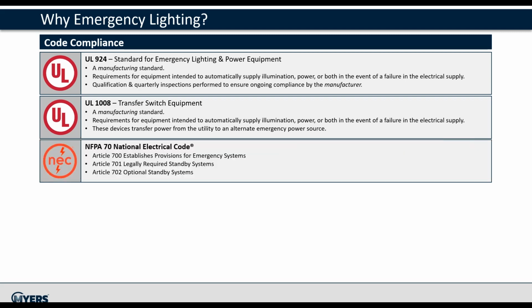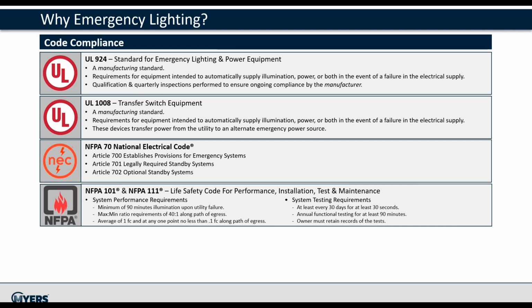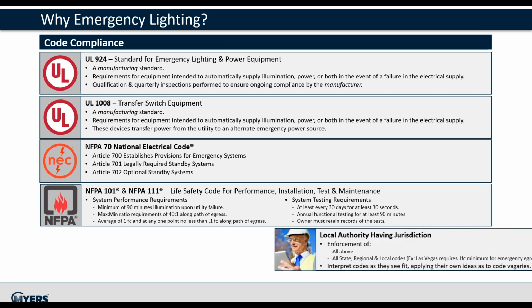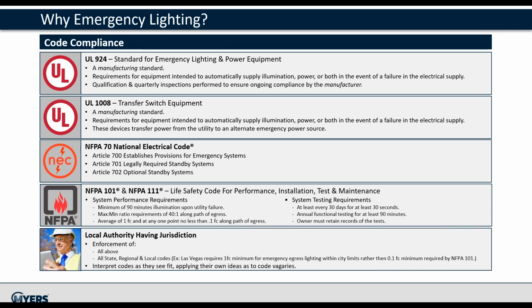The NEC or NFPA 70 codes govern the safety of the installation, operation, and maintenance of the emergency power systems, as well as optional standby systems. There are three subsections, Article 700, 701, and 702, that contain the bulk of the regulations on emergency power systems. NFPA 101 and NFPA 111 regulate the performance, installation, test, and maintenance. These codes govern the complete safety system inclusive of site requirements. Some examples are the runtime, illumination levels, average and minimum, ratio of light to dark along the path, record keeping.